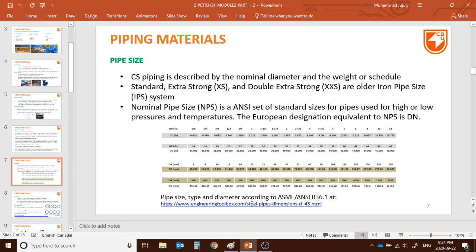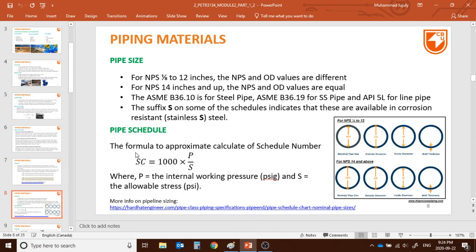You can find the full chart at engineeringtoolbox.com — it's according to ANSI/ASME B36.1. For pipe NPS 1/8 to 12, NPS and OD values are different; for NPS 14 and up, NPS and OD values are the same. The standards are ASME B36.10 for steel pipe, B36.19 for stainless steel pipe, and API 5L for line pipe.